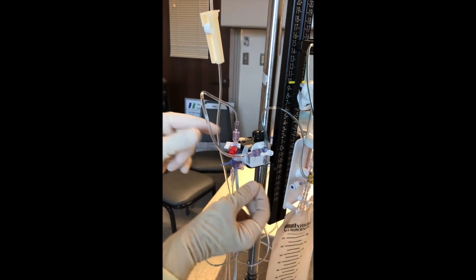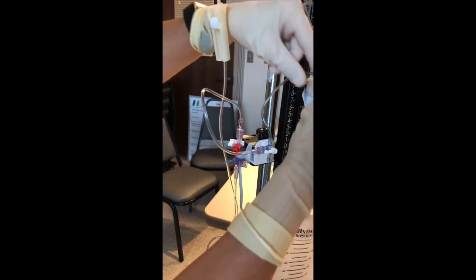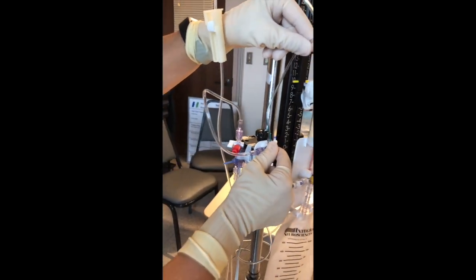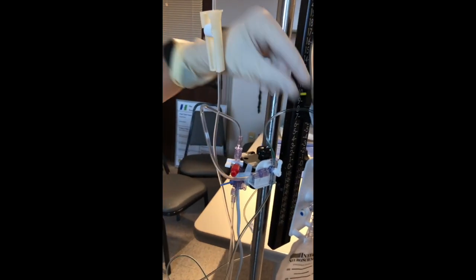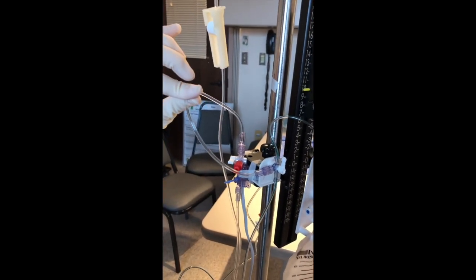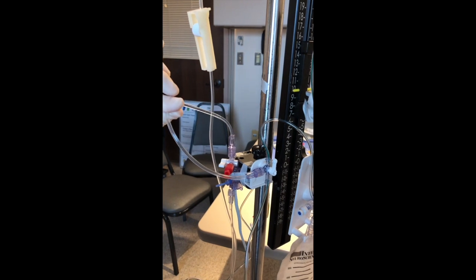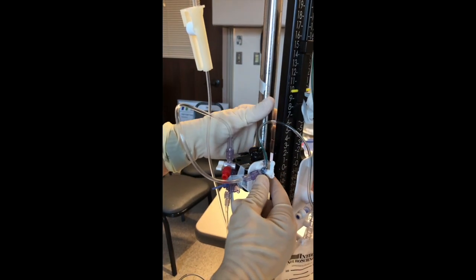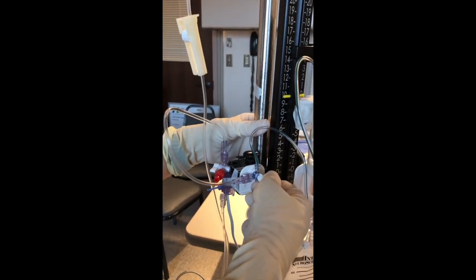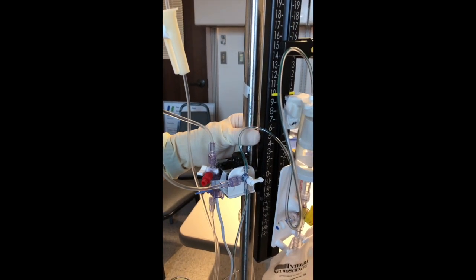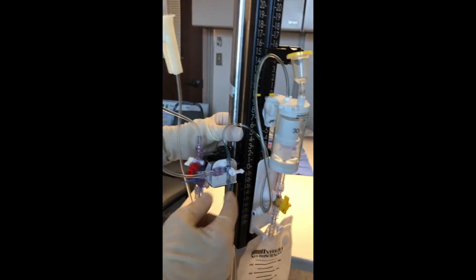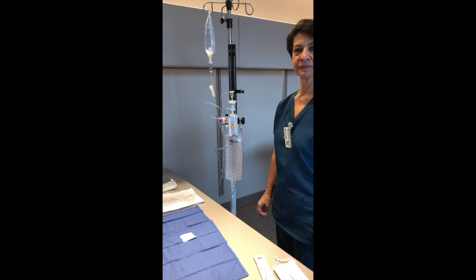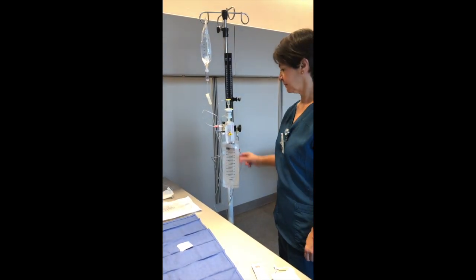If you want to measure the ICP, you close it off to the drainage, which means turn it up, and now it's connected from the patient to the pressure system. Now you can measure your ICP. The place that you never want to be in is the null position, where it's open to both drainage and ICP drainage pressure. We are now going to change the drainage bag.